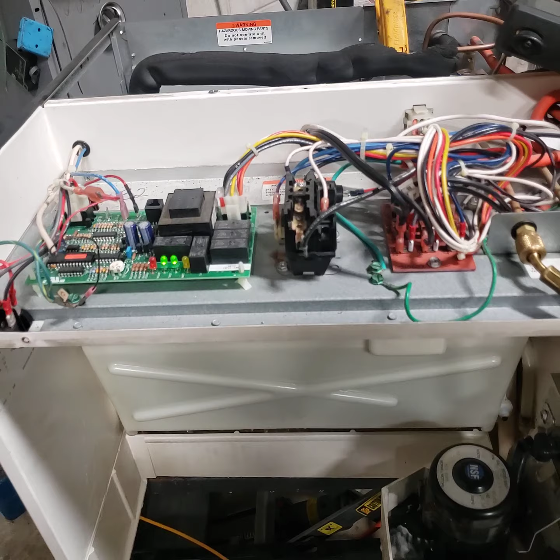So that's another issue with another story. But at least you have an idea as a restaurant owner. If you don't see harvest within an hour or so, you have a problem. So the level is still on. Basically, the water is gonna start sticking on the evaporator and building ice, and the water amount will diminish. And then this guy will shut off. I'll show you later.